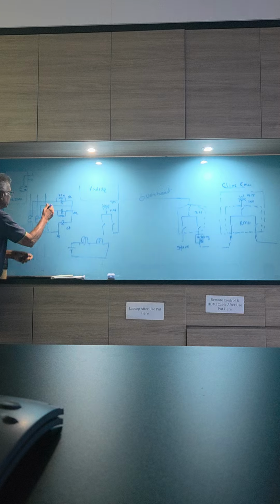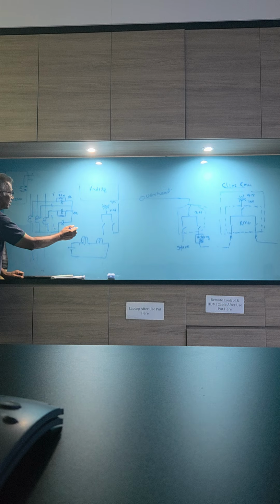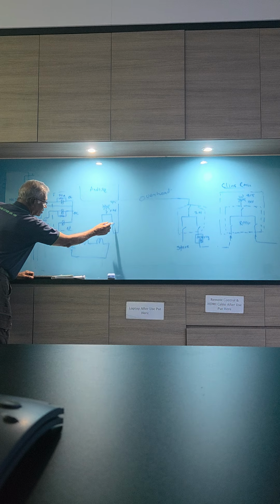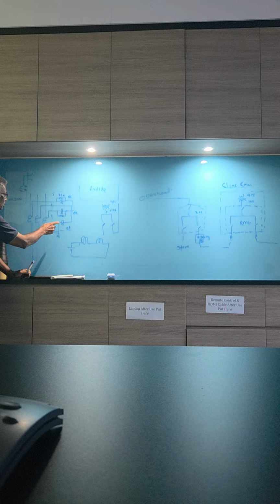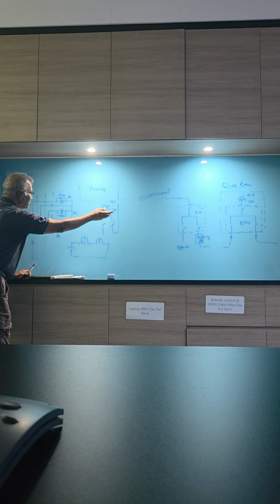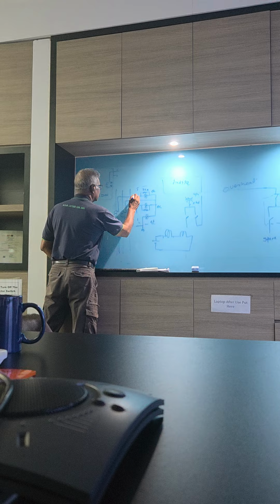This one all can be seen. This is exposed. Only the isolator is enclosed, because with 11 kV switching and all that, you cannot expose it. As for which relay, we change one relay. We come back to the junction box, we do the connection and everything. Then we put back the wiring as it was earlier. So when the calibration people injected current, it didn't trip. None of these three shunt trips worked. Didn't work at all.